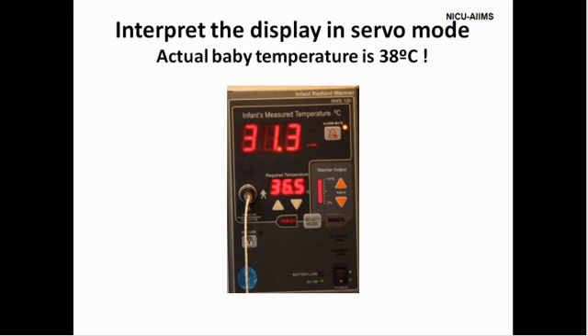Let us see this clinical example. Can you interpret this display? The actual baby's temperature recorded is 38 degrees Celsius. Did you get the answer? Well, the warmer is in servo mode, as you can see. The set temperature is 36.5 degrees Celsius. Most probably, the skin probe is out and this probe is displaying the air temperature. You can also see that the heater output in this condition is maximum, thereby the baby has been overheated and the baby's recorded temperature is 38 degrees Celsius.